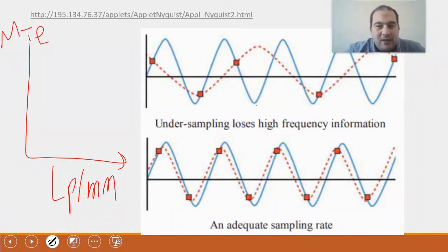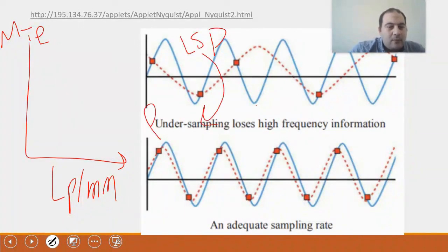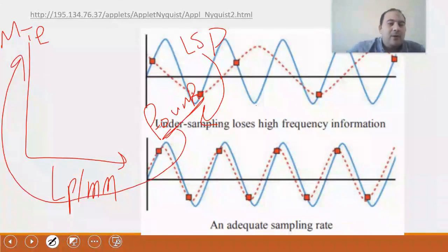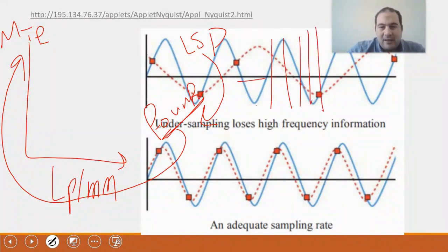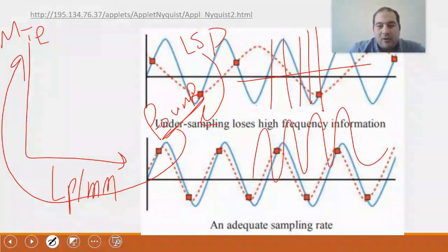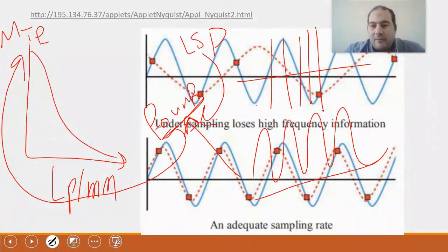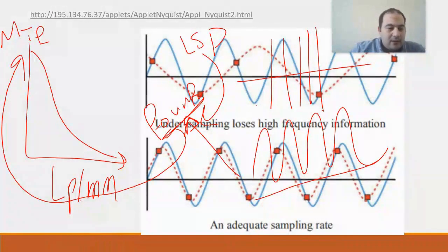As we said, the value of the MTF needs to be calculated. And to do that, you have to use something called the line spread function. The line spread function is then input into something called the Fourier transformation, which gives me the value of the MTF. This is a big topic with more details, but it relates to what I was explaining last time to Dr. Hani. I told him that I take a line, and this line gives me something called a line profile. Okay, this is the frequency, and this frequency is transformed by the Fourier transformation into the MTF curve like this.